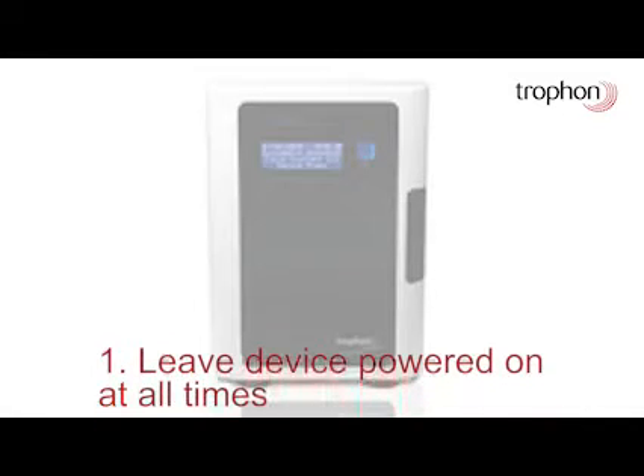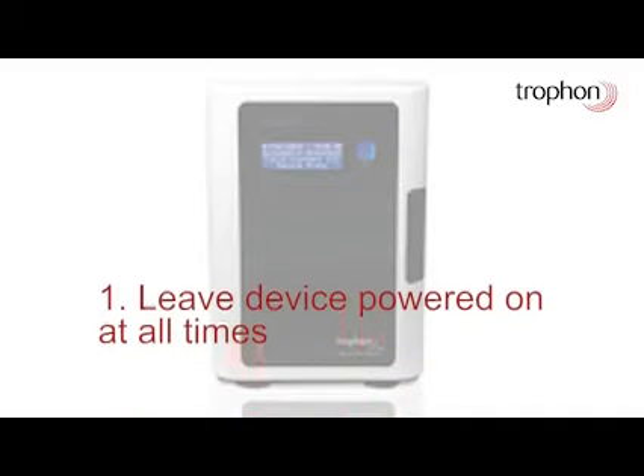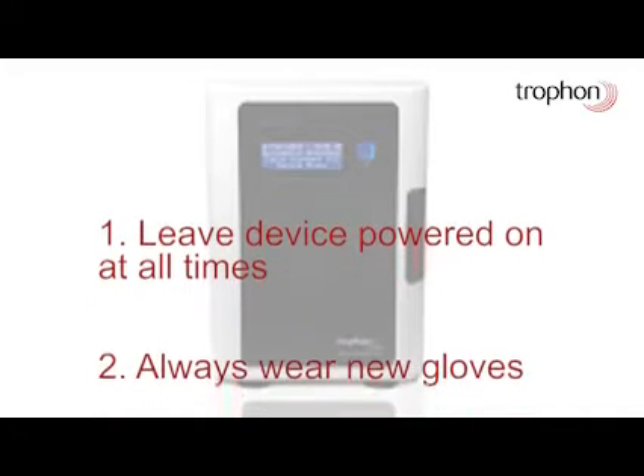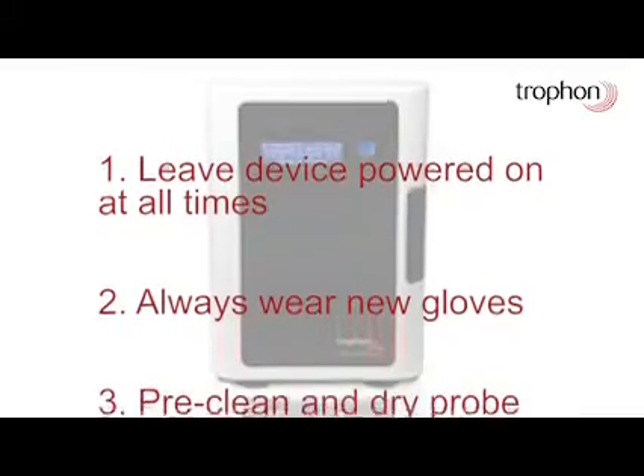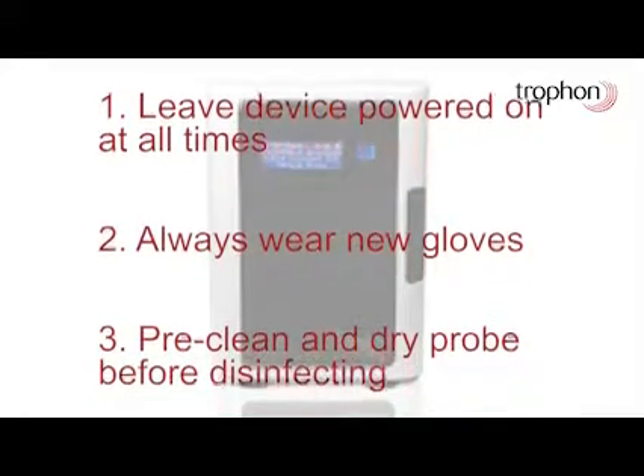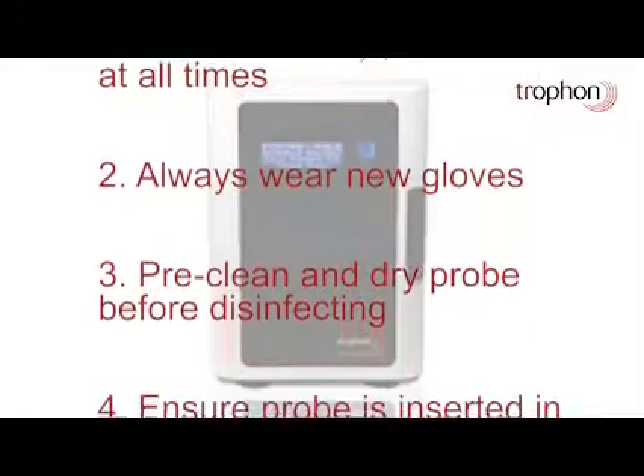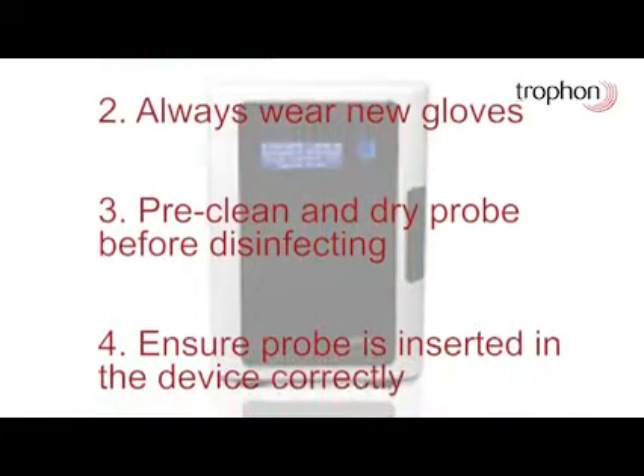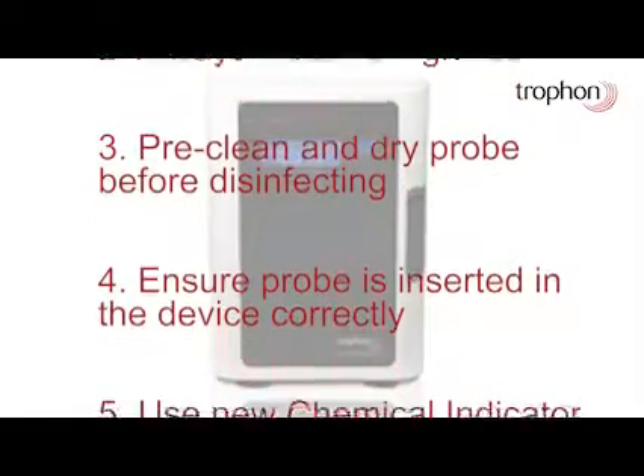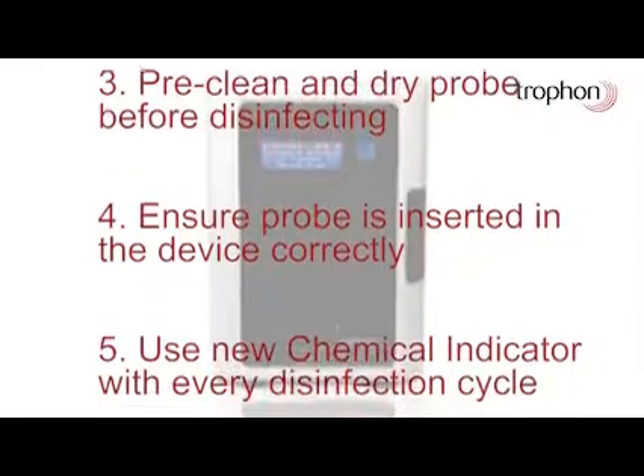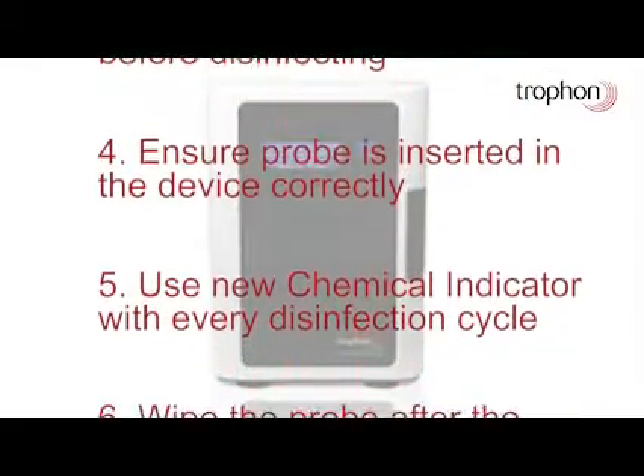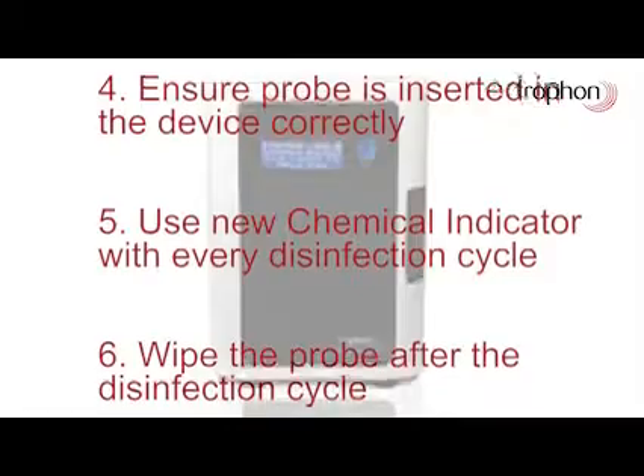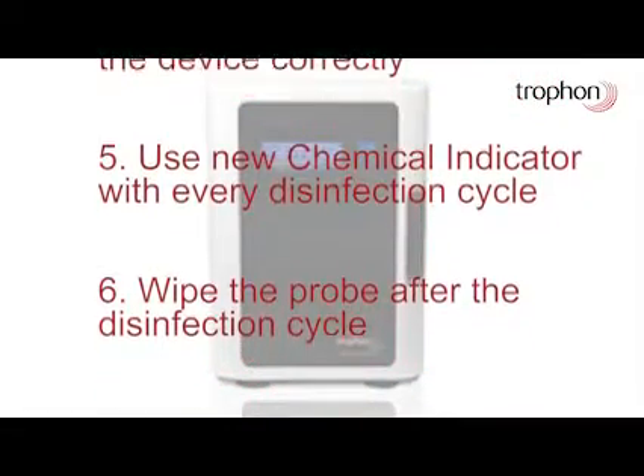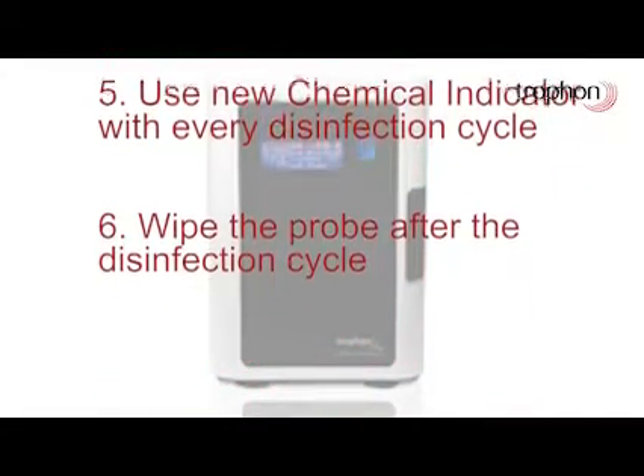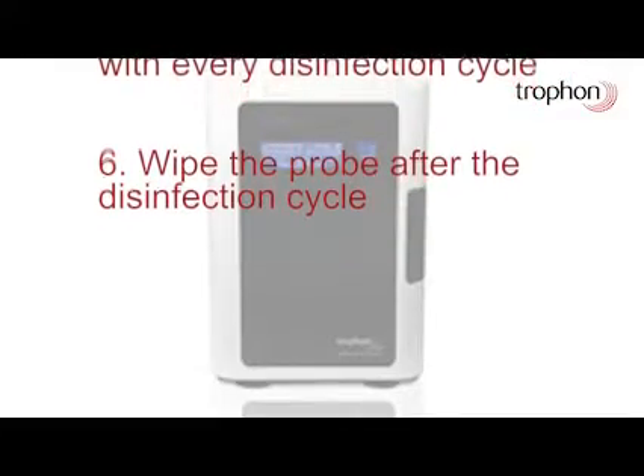To summarize what you have learned today, let's review some of the key points. Leave your device powered on at all times. Always wear new gloves. Pre-clean and dry the probe before disinfecting. Ensure the probe is inserted in the device correctly. Use a new chemical indicator with every disinfection cycle. Wipe the probe after the disinfection cycle.